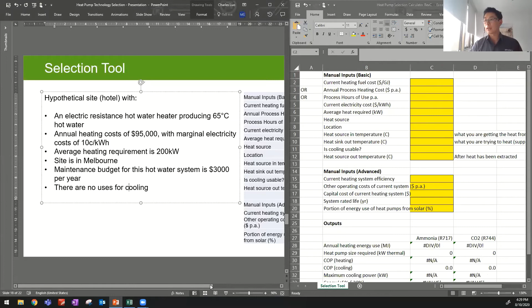So let's enter the example. Here we've got the input fuel heating cost in dollars per gigajoule. So we've got to convert that from 10 cents per kilowatt hour to dollars per gigajoule. I've done that legwork, and it's $27.80 per gigajoule. We've got the annual heating budget, so the energy use of $95,000, and you'll see that this is blanked out. We only need one or the other.